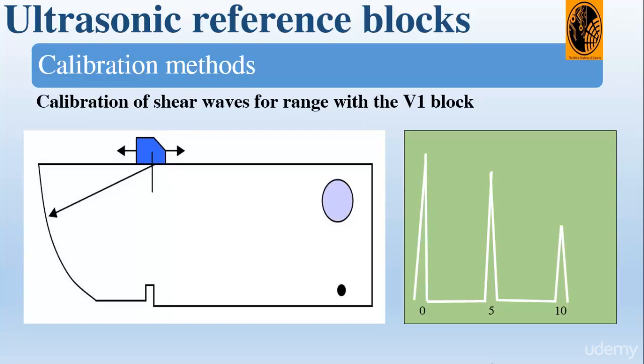First we place the probe on the V1 block and obtain the boundary echoes from the 100 millimeter radius, then establish the signal to more than 50% height using the gain control and maximize the echo by moving the probe backwards and forwards. Then we zoom in or out using the scale expansion range control to establish a second boundary echo at 200 millimeters. We place the signal from the 100 millimeter mark at position 5, which is half scale on the time base, and the signal from 200 millimeters at position 10, which is full scale, using the delay and range controls.